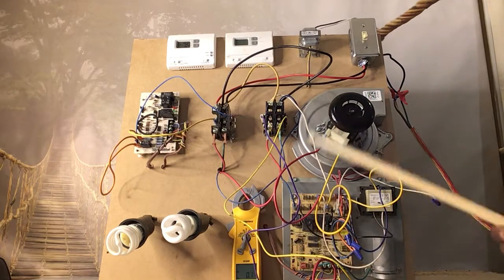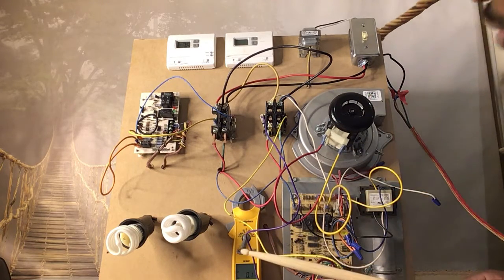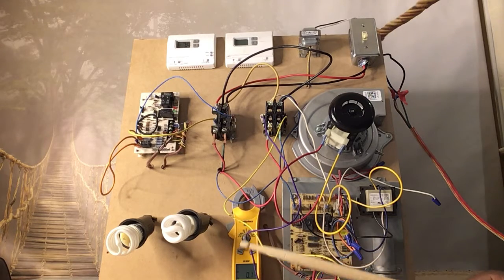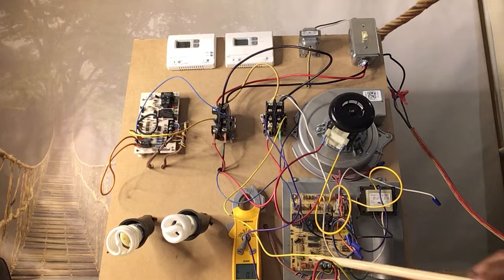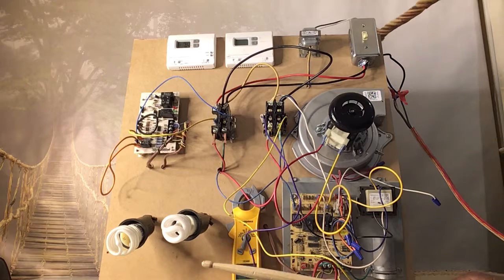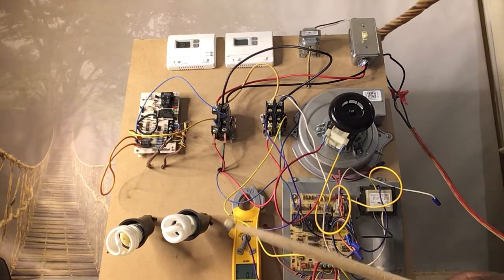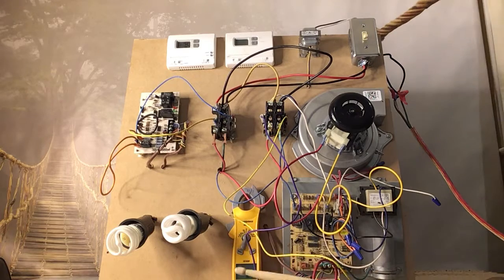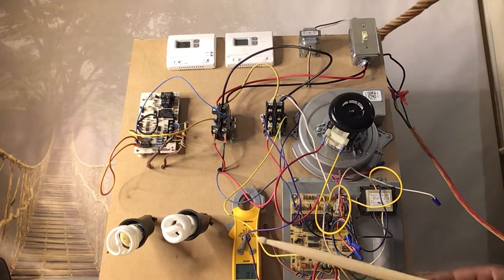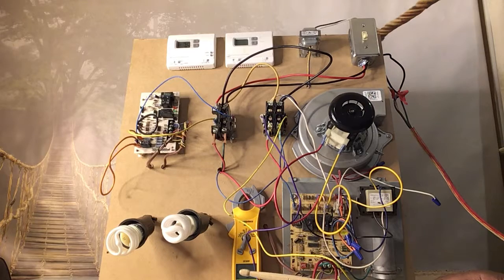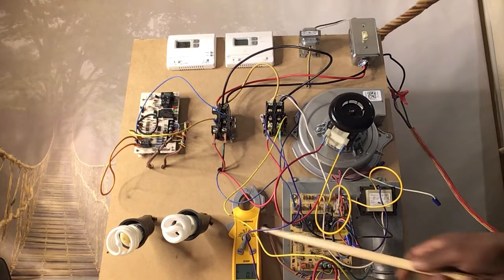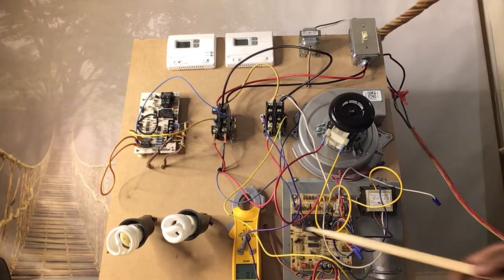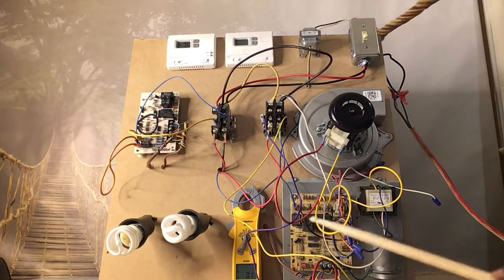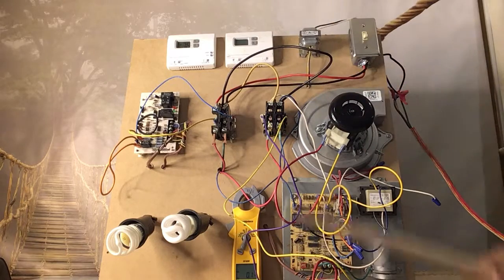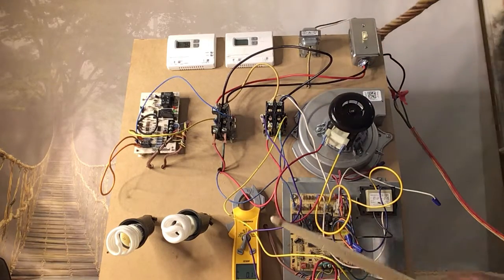Underneath that is also a control board that you will find inside of a gas furnace. What happens here is that it gets 24 volts, and then the control board kind of has a mind of its own. It'll run through some cycles and then in turn turn on this fan. So the purpose of this particular video is just to teach you guys how to utilize a voltmeter, which is this right here. This is your voltmeter. You would utilize that to check power across your board to verify any defects in troubleshooting.